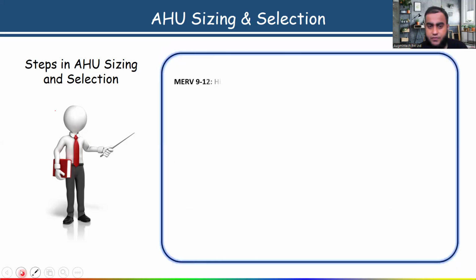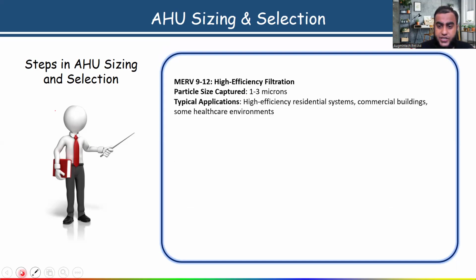Next, we have other filters like the MERV 9 to 12 rating filters. It is our high efficiency filtration. It can capture 1 to 3 micron particles. Particle size capture is 1 to 3 micron. And the typical application is given here, where we can use this type of filter: high efficiency residential systems, commercial buildings, and it is special for healthcare environments. For healthcare environments, this type of filter is generally used.